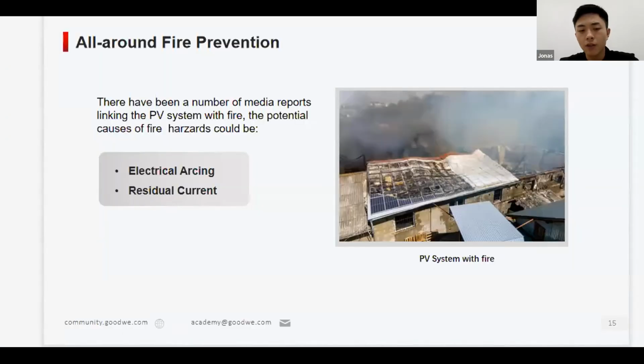Over the past few years, there have been many media reports linking PV systems with fire. Until now, nearly 200 gigawatts of PV systems are installed all over the world, and an increase in incident reports is to be expected. These fire incidents have a marked impact on people and property. It's very important for us to understand the likely mechanisms of ignition in PV systems. The potential causes of fire hazards could be electrical arcing and residual current, and so on. There are many reasons that could cause fires, for example very hot temperature and improper installation.